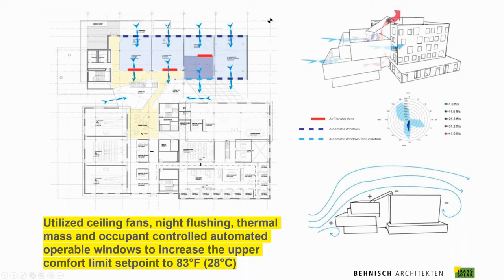For the rest of the spaces, air comes in through automated windows that open once the building goes into natural ventilation mode. A transfer vent carries air into the atrium space. We designed the exhaust point as the most negative point of the atrium — we peaked above the existing building where the wind creates negative pressure. You never want your exhaust point for your natural ventilation system to face directly into the windward side of the building. You always want to create a little negative pressure zone so that air releases as freely as possible and doesn't get pushed back inside.